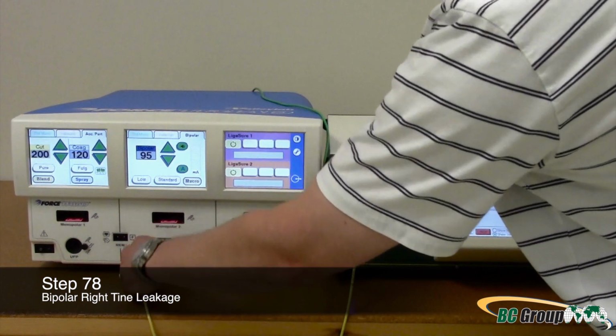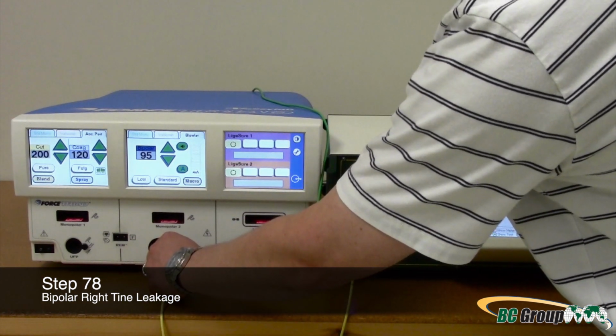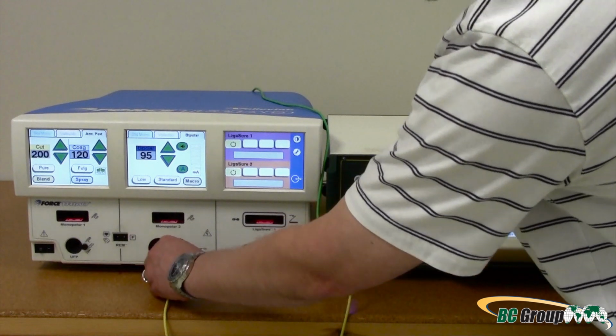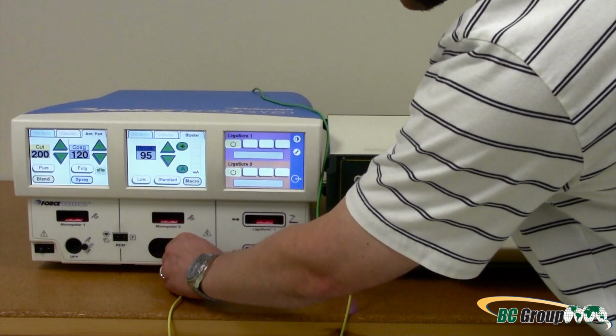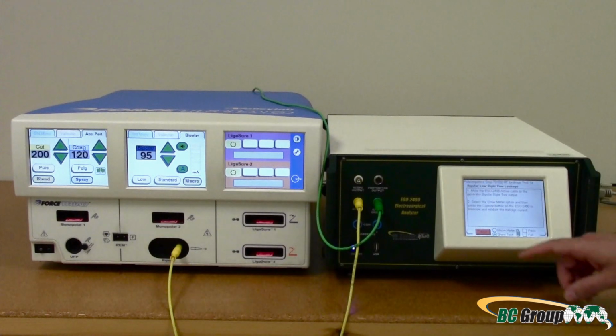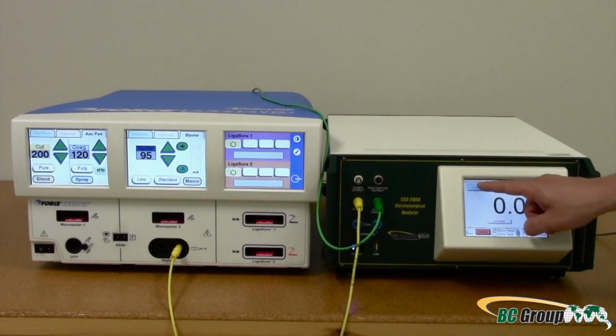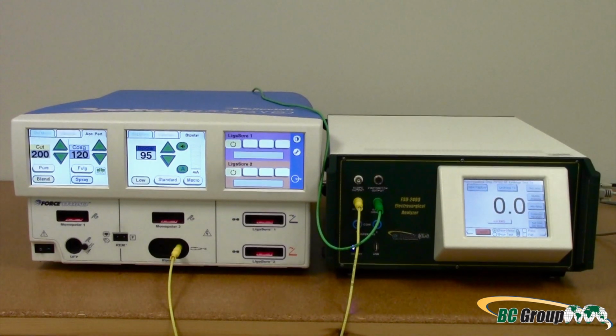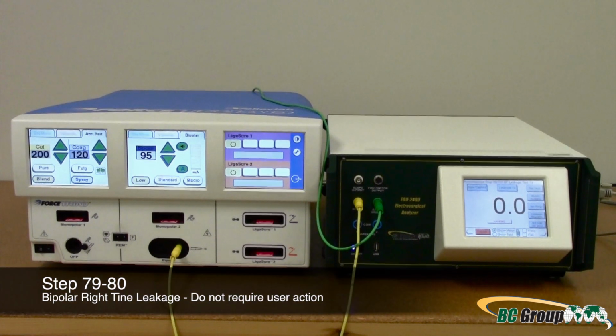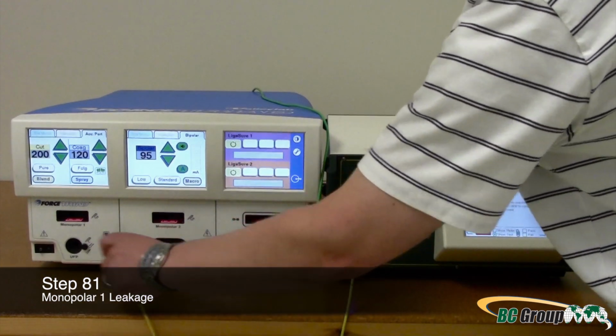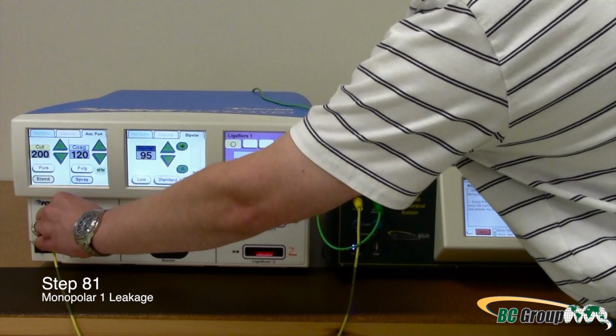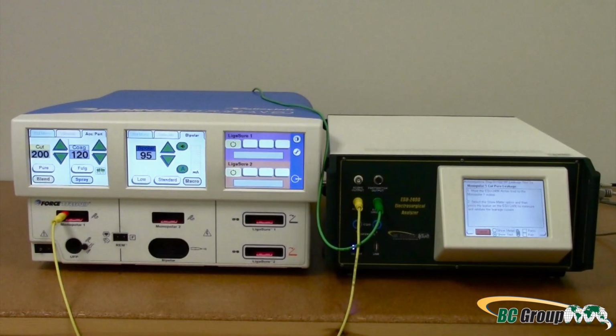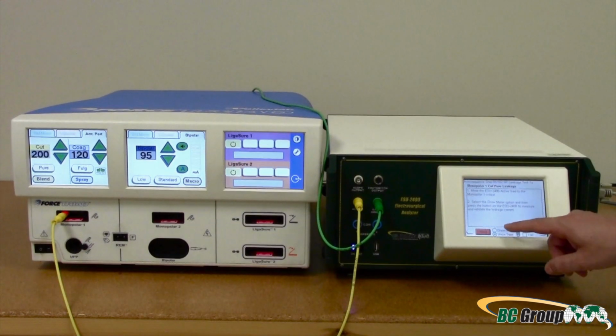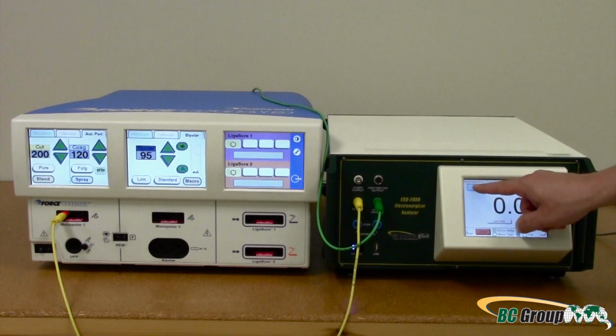Step 78. Bipolar right tine leakage. Move the ESU-2400 active cable to the right tine of the bipolar port. Select Show Meter and then press Capture. Steps 79 through 80 do not require user action. Step 81. Monopolar 1 leakage. Move the ESU-2400 active lead to the Monopolar 1 output. Select Show Meter and then press Capture.